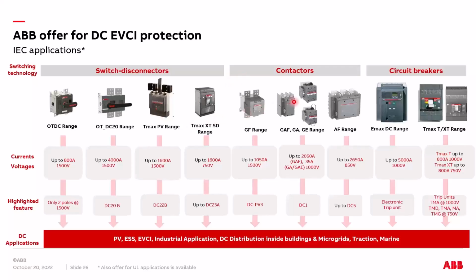We also have a contactor, which normally can be installed on the DC charger in order to guarantee a higher number of operations in load condition, I mean with the current, and also circuit breakers, both the so-called air or power circuit breaker with electric current up to 5,000 amps at 1,000 volts, and circuit breakers in a so-called molded case configuration with a lower electric current, but with a higher number of operations in load condition.